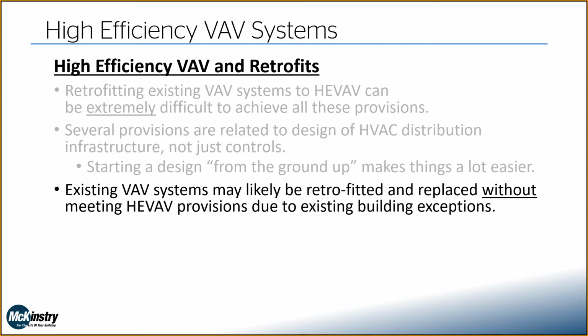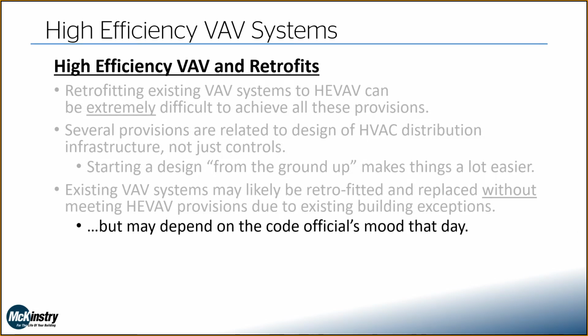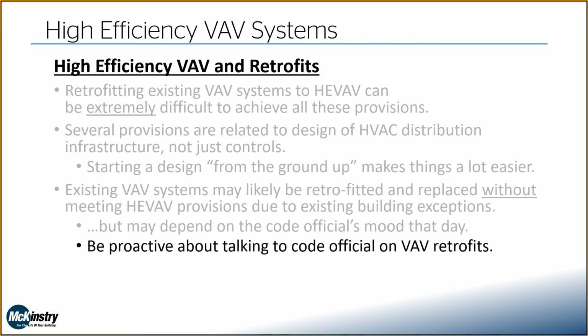So you can make a pretty strong argument that you shouldn't have to turn an existing VAV system into high efficiency VAV, but you may get a code official who is just really adamant and is going to fight you to make this happen. So ultimately, it's good to be proactive about talking to that code official on any VAV retrofit project. Because if you get towards the end of the design, assuming you don't need to do this, and then the code official is going to try and make you do it, that's a pretty substantial change in design that you don't want to have happen at the 11th hour.